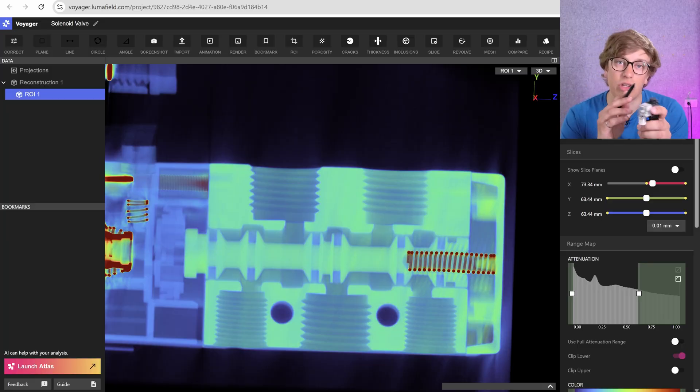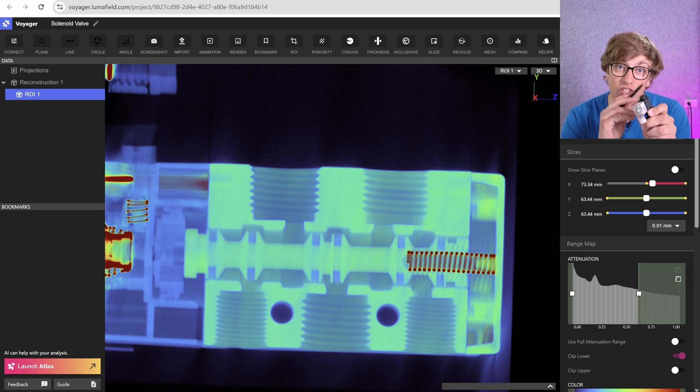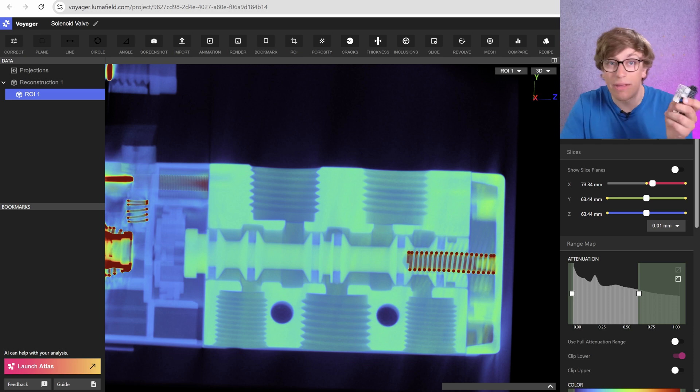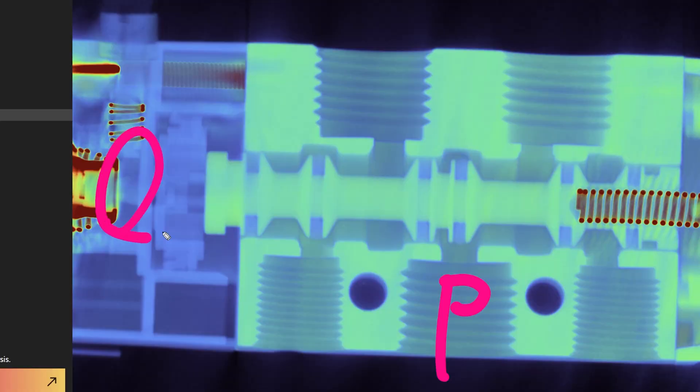Luckily, this is a pneumatic system, so we have a supply of compressed air going into P. If we can tap some of that and have a smaller valve controlled just by the solenoid over here, well that can drive this entire spool back and forth using our 150 psi air supply.